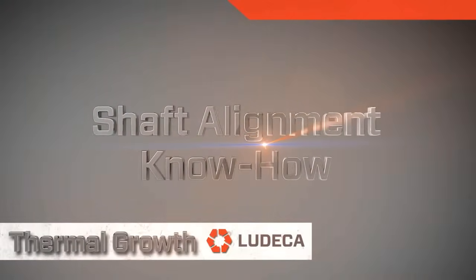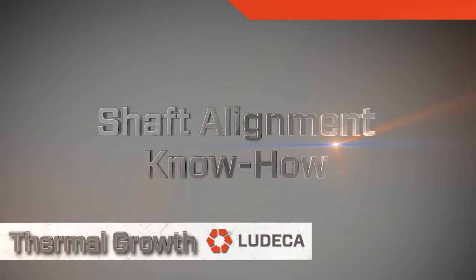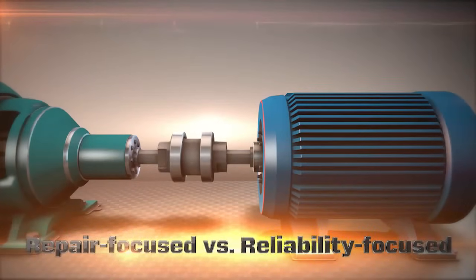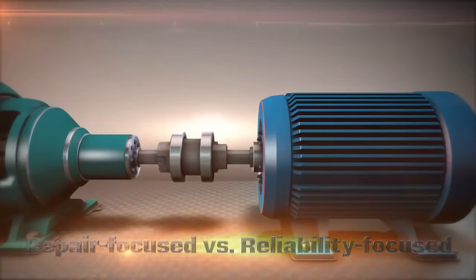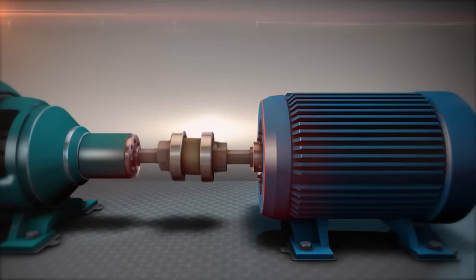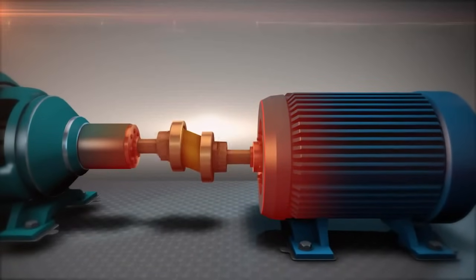Shaft alignment know-how: Thermal growth. Positional change. Not accounting for positional change in rotating machinery is a big reason why maintenance departments stay reactive instead of proactive. When rotating equipment runs, it heats up and undergoes positional changes.